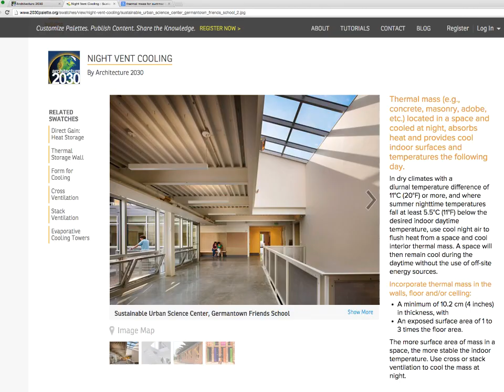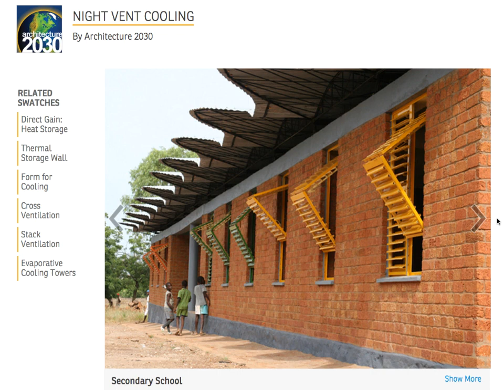Now, during the daytime especially, and especially when the building's occupied, you have lights, you have people, you have equipment. All these are producing internal gains. You have solar gain coming through the windows. That's usually a big one. And you have some conduction gain coming because it's hotter outside than it is inside. So all these are contributing to the building's rate of heat gain. When the building is closed, you have to do something with that heat gain. If you're not going to air condition it, then what we do with it in this case is store it in the mass. So the mass begins to absorb those heat gains hour by hour across the day. The mass then has to be big enough to store that daily rate of heat gain.